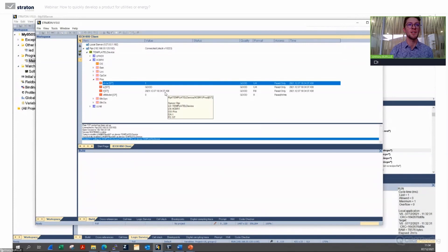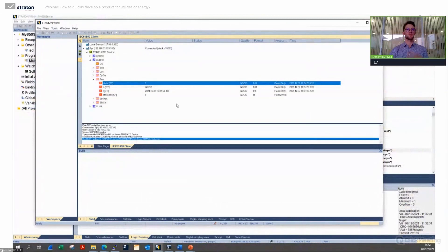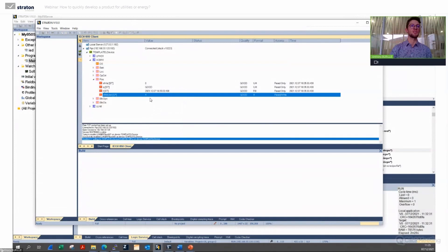I click OK, connect to the server, and I can see everything available on the server. Even though I mapped only a few variables in my application, I can see everything from the client side. Going to the circuit breaker position, I can see it's blinking — the timestamp is updated with the right date — stVal is blinking from zero to one, just like in my 61850 server application.